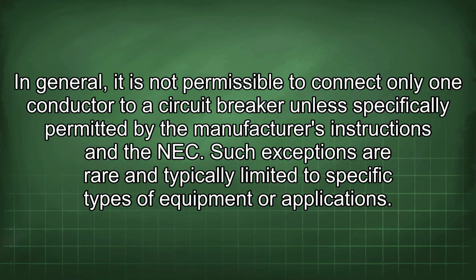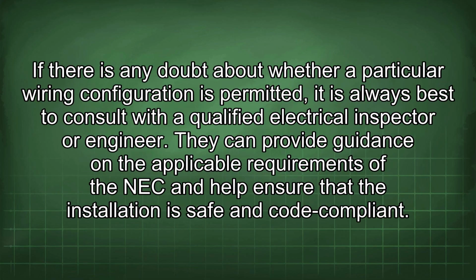In general, it is not permissible to connect only one conductor to a circuit breaker unless specifically permitted by the manufacturer's instructions and the NEC. Such exceptions are rare and typically limited to specific types of equipment or applications. If there is any doubt about whether a particular wiring configuration is permitted, it is always best to consult with a qualified electrical inspector or engineer.